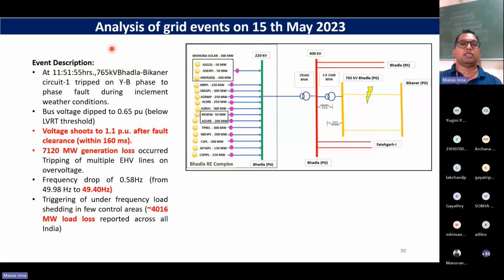So I will be analyzing one use case, of 15th May 2023, a grid event near the Rajasthan area, the renewable energy complex. For the event description, please look at this diagram. It was a fault case on this particular line: at 11:51, the 765 Bhadla Bikaner circuit 1 tripped on a phase-to-phase fault.